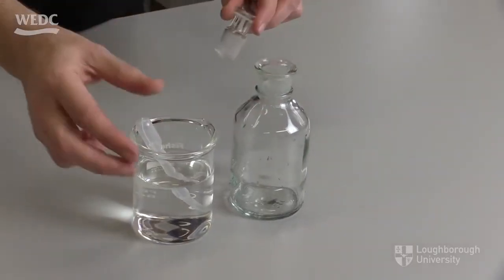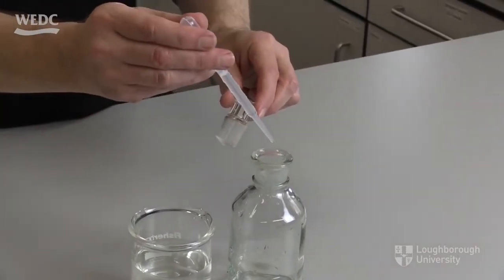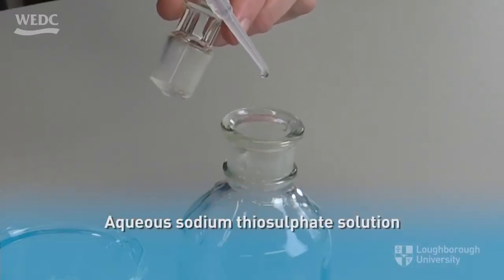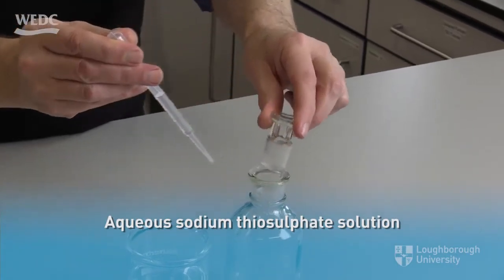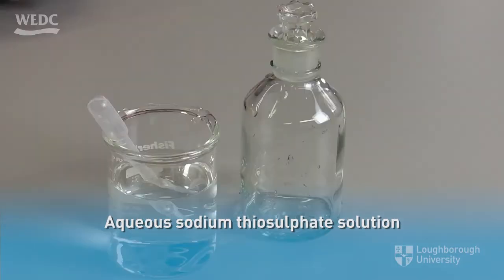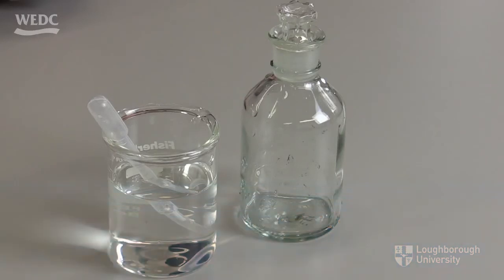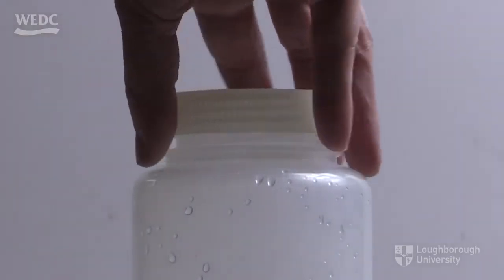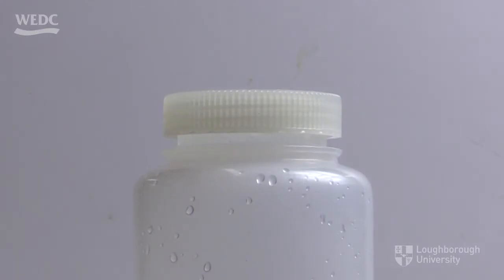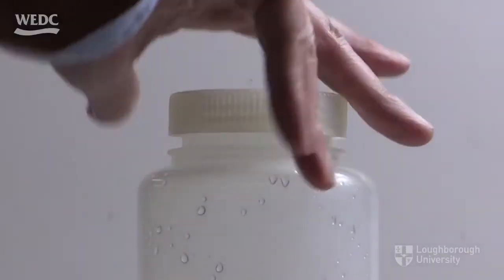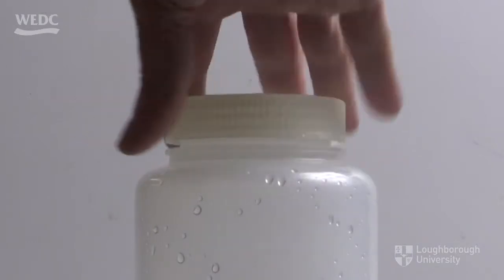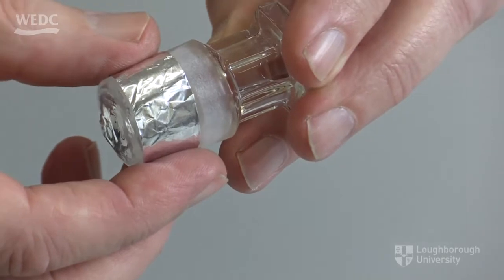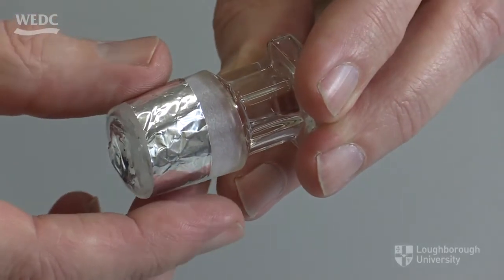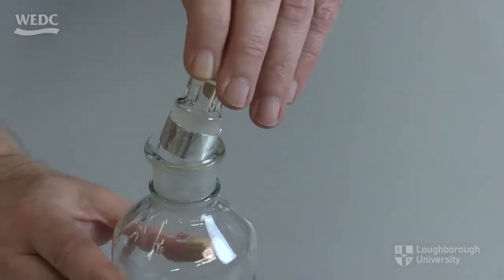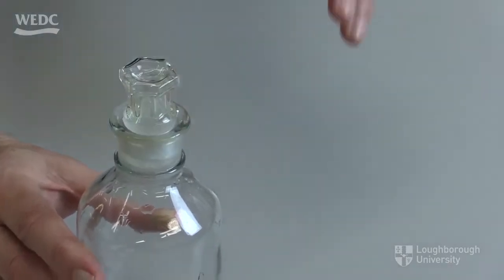Next, for a 200 milliliter sample, add 4 or 5 drops of aqueous sodium thiosulfate solution to neutralize any residual chlorine, which could distort the results of the analyzed sample. Screw bottle caps should only be loosely fastened prior to sterilization, and then only tightened when they have cooled following sterilization. For a ground glass bottle with a stopper, a strip of paper or aluminium foil should be placed inside the neck of the bottle to prevent the stopper from getting stuck during sterilization.